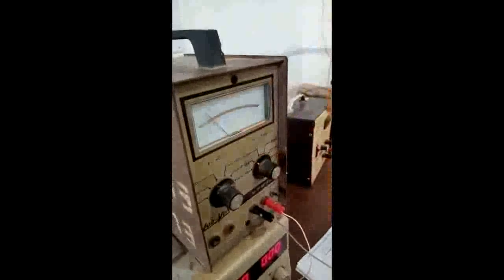Don't make the mistake of counting this one to be 1 point something in milliamp. No, everything here is 1. I'm using the upper scale. This is 1.5, but it's not 1.5 milliamps, it's 0.15 milliamps. Everything here is 1. This one is 0.1, 0.2 like that. Now we have less than 1. This is 0.15 milliamps. That's the current reading.